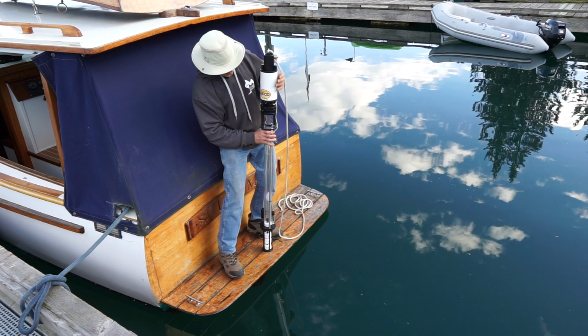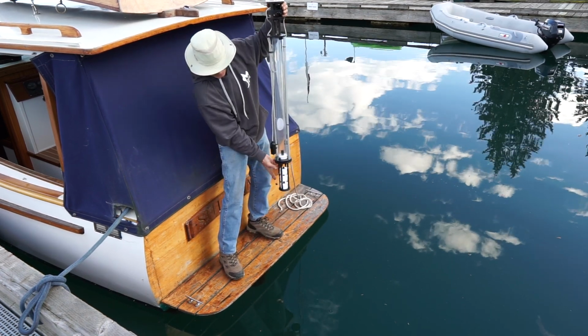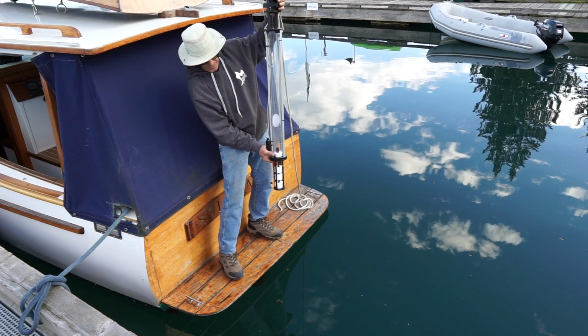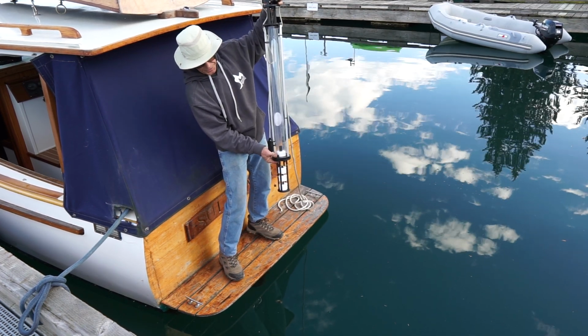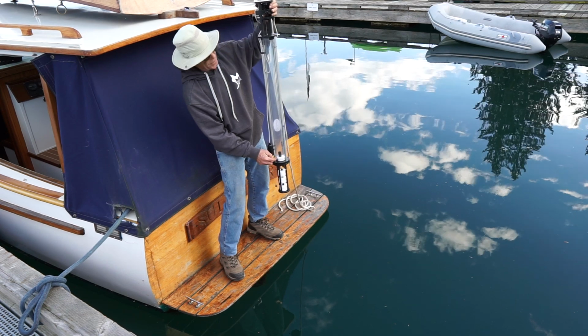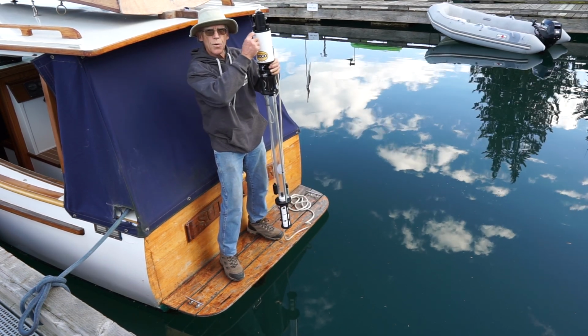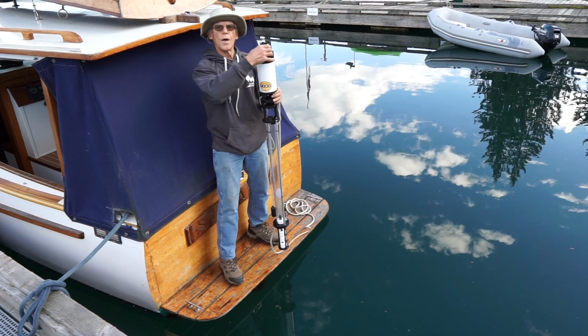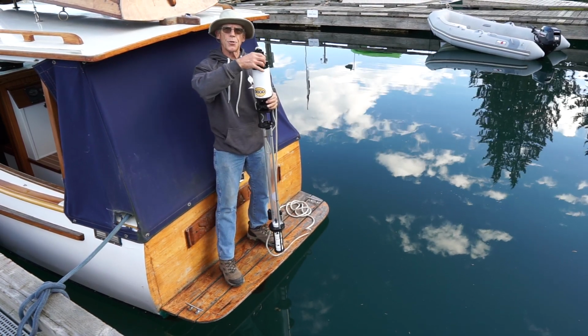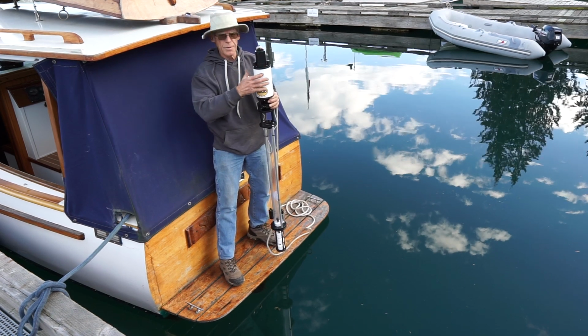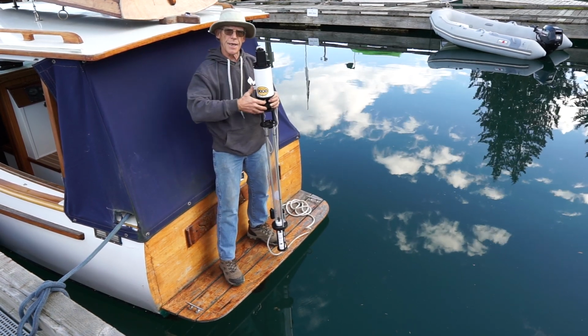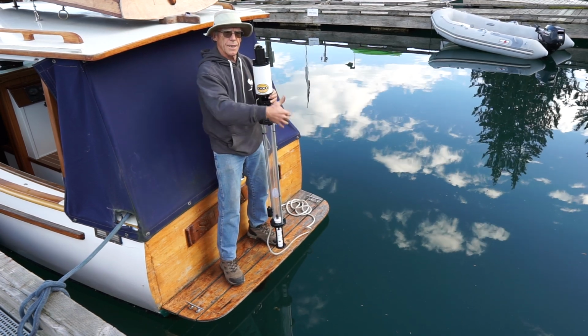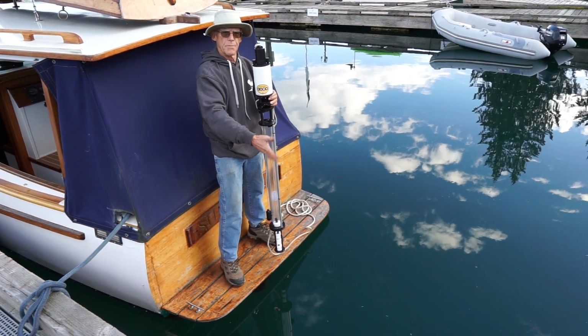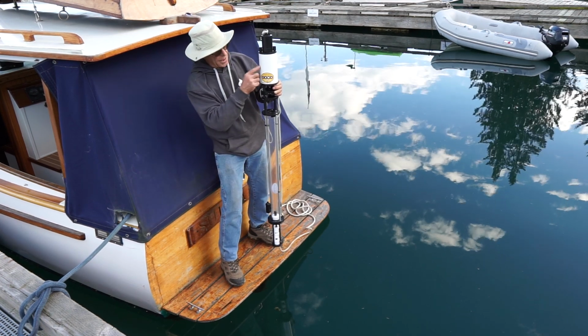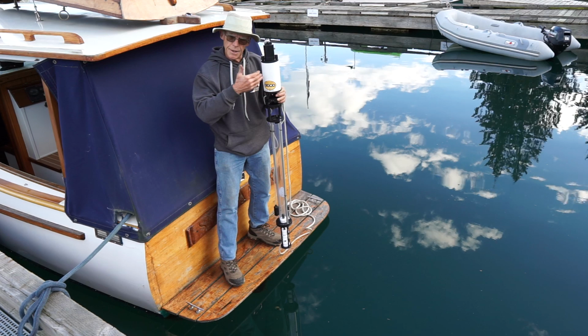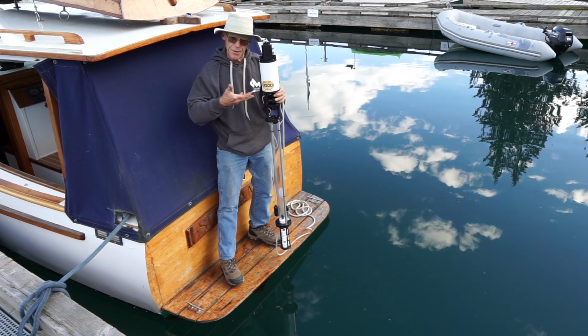Or how it operates is there's plugs sitting in the plug carrier down here. The first plug is inserted into the tube, and there's a wire that runs from the top of the plug to the winch that's inside the pressure housing. 12-volt battery in here, rechargeable, and that provides our power. The unit's totally independent, so it can be set, lowered, or set and attached to a ROV or a manned submarine. So I'll set the depth for the sample to 3 different depths: 3 meters, 6 meters, and 9 meters of depth.